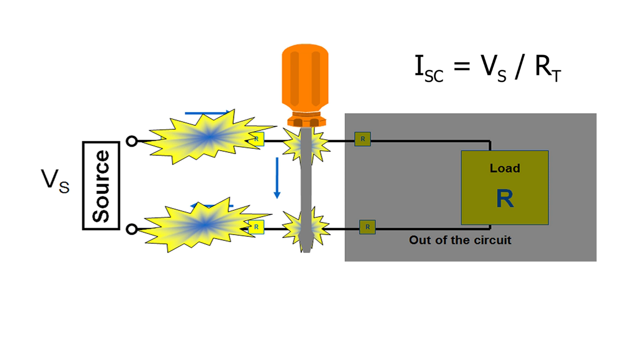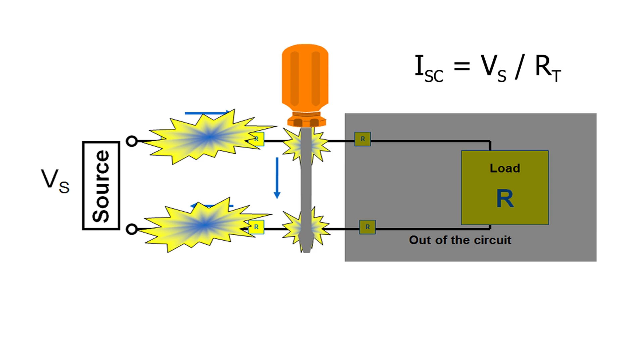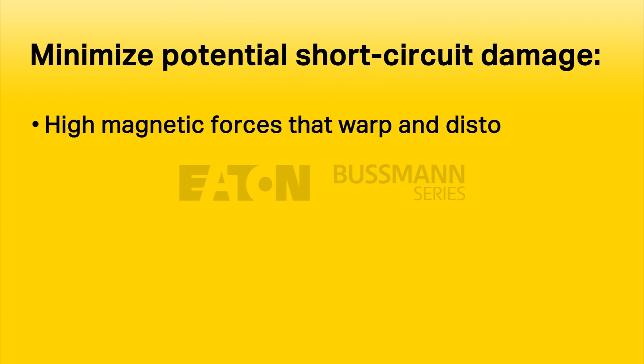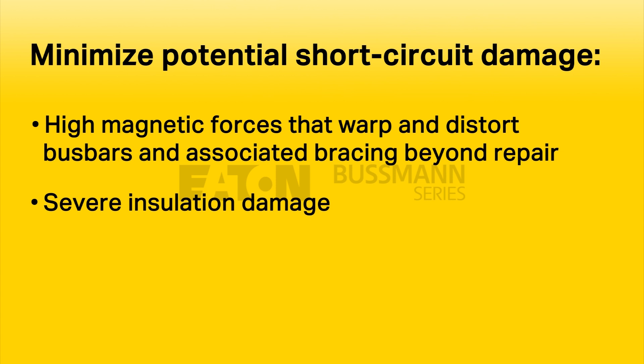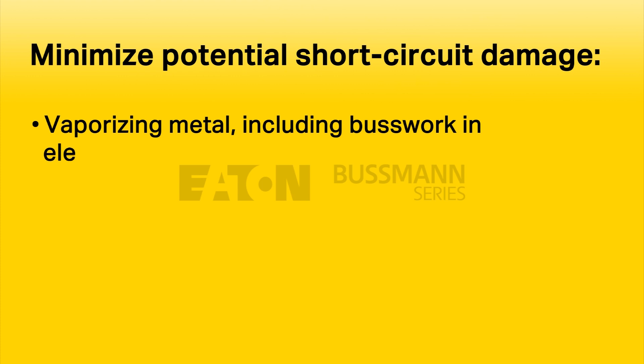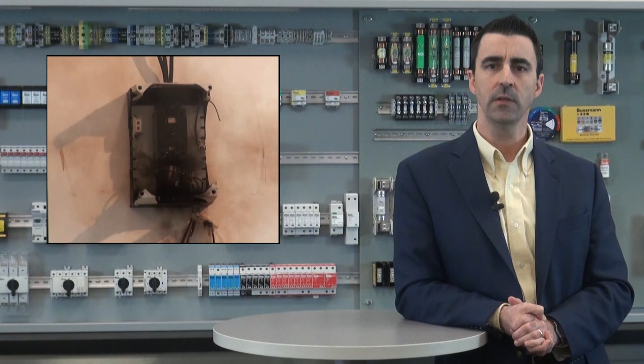A high-level short circuit may be up to 30,000 or even 200,000 amps and must be interrupted as quickly as possible to minimize damage. This could include high magnetic forces that warp and distort bus bars and associated bracing beyond repair, severe insulation damage, melting or vaporizing conductors, vaporizing metal, including buswork and electrical equipment, ionizing gases, arcing fires, and explosions. An understanding of what happens during a short circuit is important to properly apply equipment and protective devices.